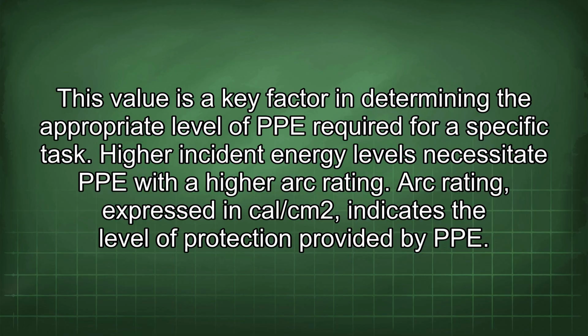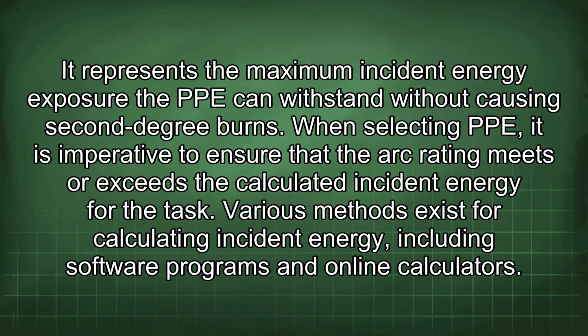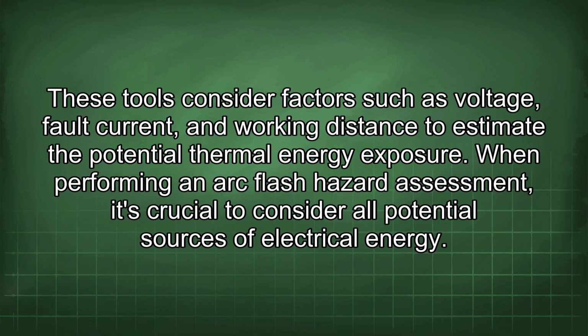Higher incident energy levels necessitate PPE with a higher arc rating. Arc rating, expressed in cal/cm2, indicates the level of protection provided by PPE. It represents the maximum incident energy exposure the PPE can withstand without causing second-degree burns. When selecting PPE, it is imperative to ensure that the arc rating meets or exceeds the calculated incident energy for the task. Various methods exist for calculating incident energy, including software programs and online calculators. These tools consider factors such as voltage, fault current, and working distance to estimate the potential thermal energy exposure.